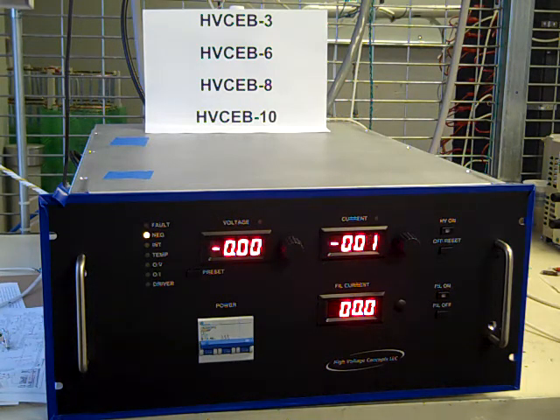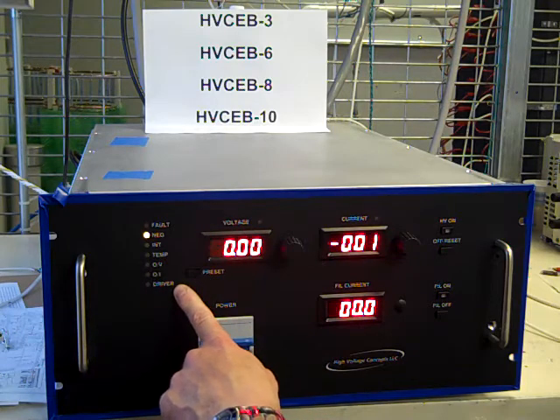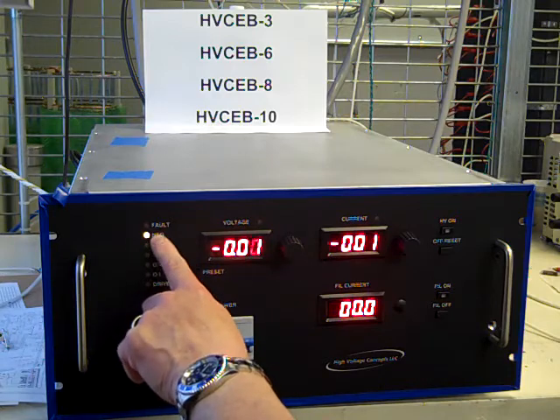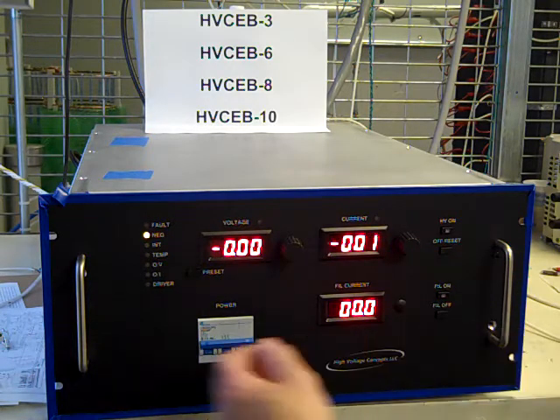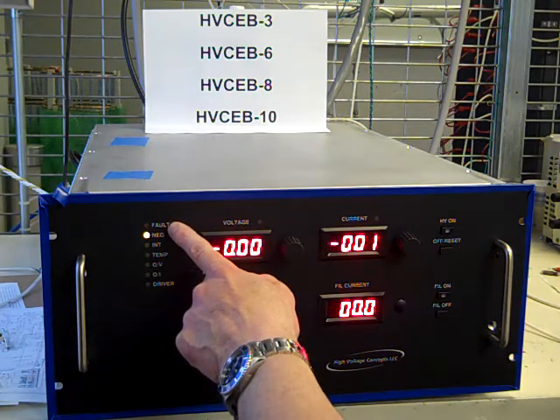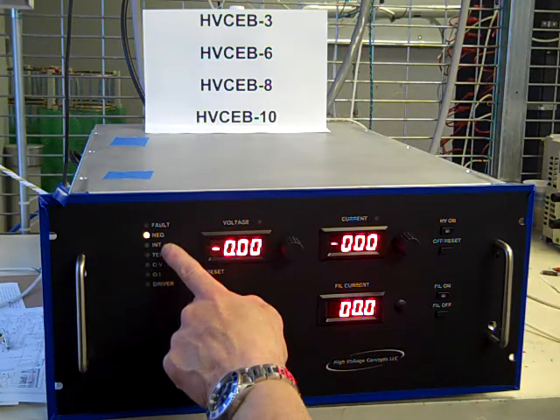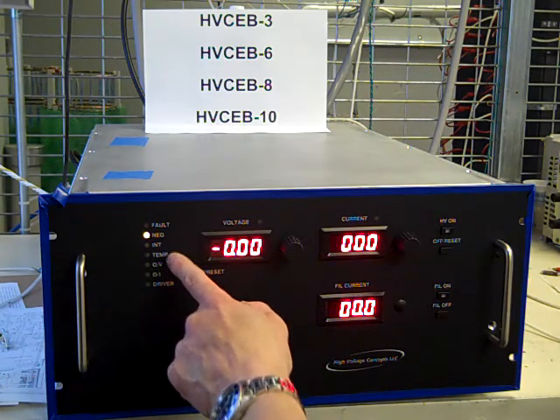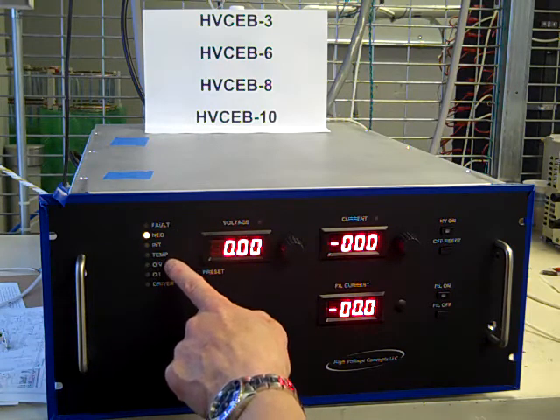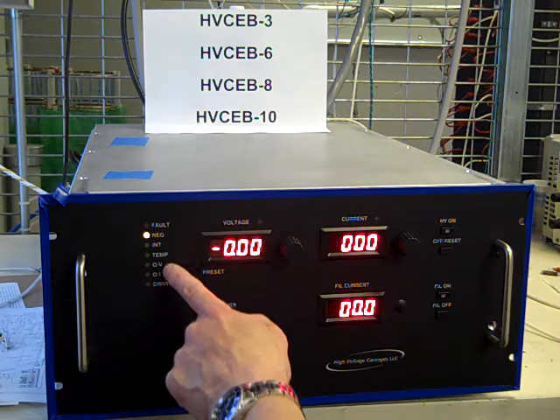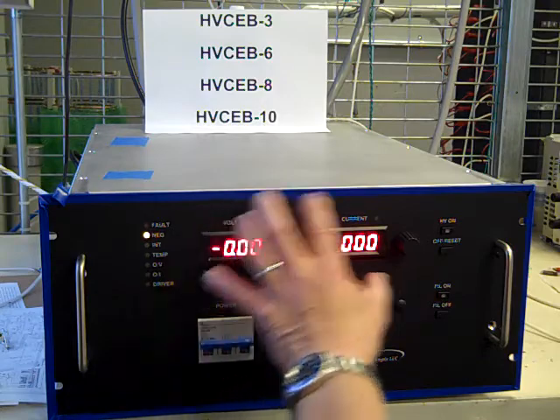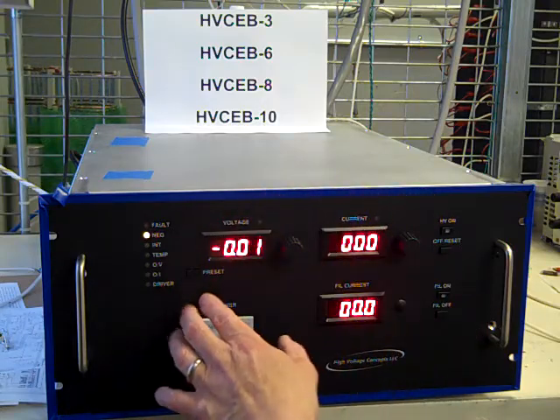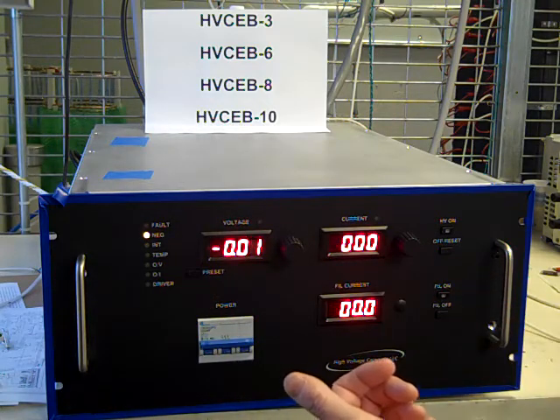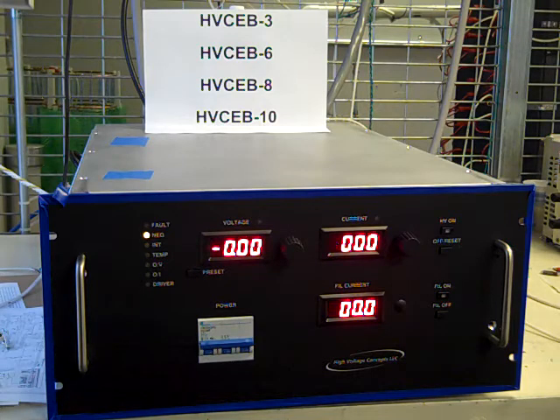And as you can see, we have a series of faults that can occur. This negative light represents the polarity of the power supply. All the E-beams are negative. This fault light, if any one of these faults is triggered: an interlock, over temperature, because the power supply monitors its own temperature, over voltage or over current. These almost never fire. If these fire, it means that the regulator somehow got out of control. The last one is a driver. That could be an overcurrent, a short circuit on the output, or it could be a very high peak current.